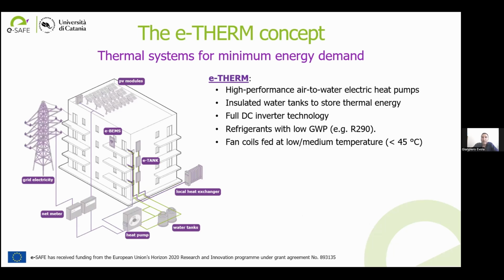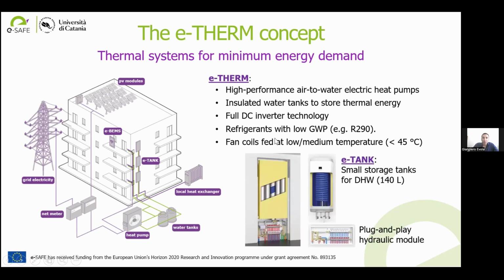Well, in this framework, our e-THERM system that we are developing and testing in the eSafe project is based on centralized air-to-water pumps that are assisted by electric batteries and large water storage tanks, centralized storage. So we store thermal energy and electric energy, both. We use refrigerants with low GWP, so propane in this case. But what is interesting is that we also use a second level of thermal energy storage, which is decentralized. In each dwelling, we install a small, slim storage tank called e-tank. My colleague Giovanni Semprini will talk about it later. This tank is used to store domestic hot water locally. It also has a plug-and-play hydraulic module inside, which helps facilitate its installation.